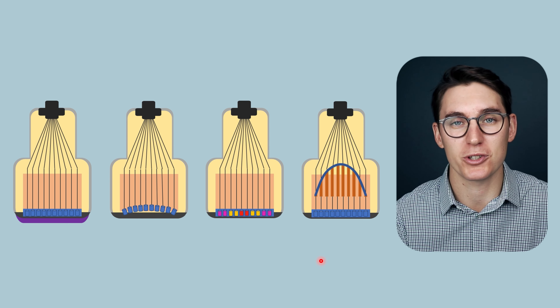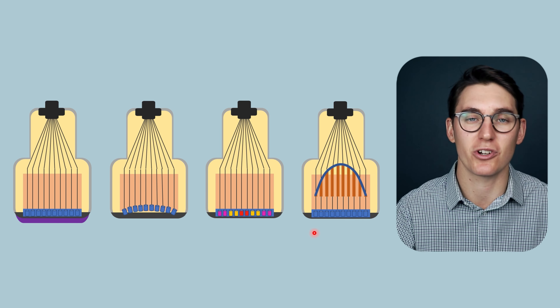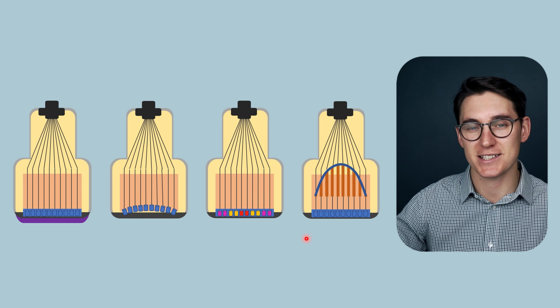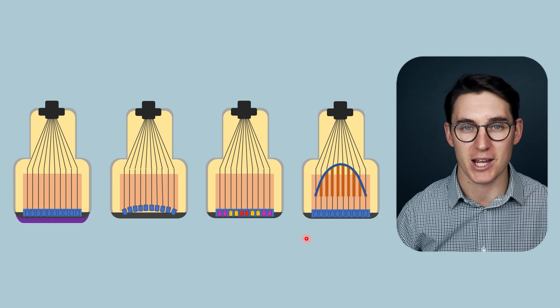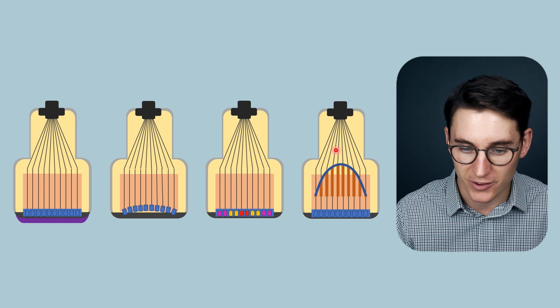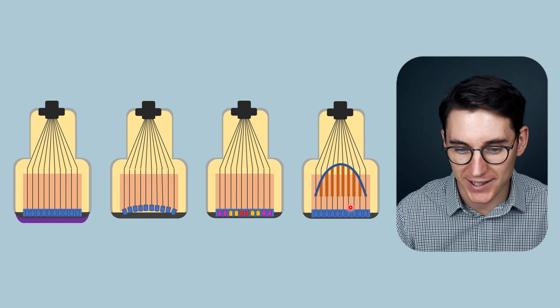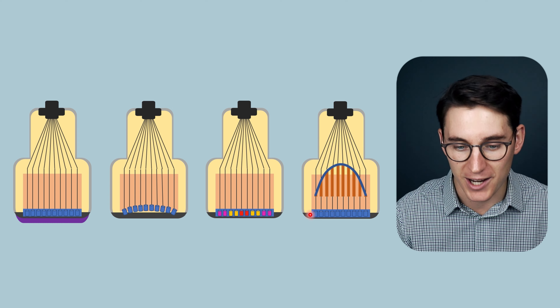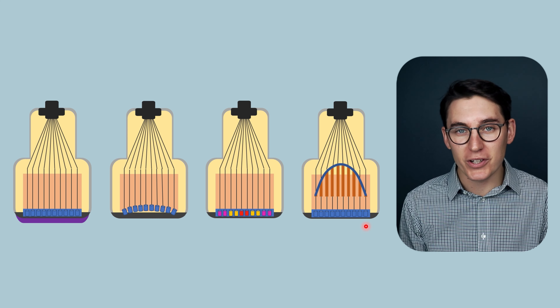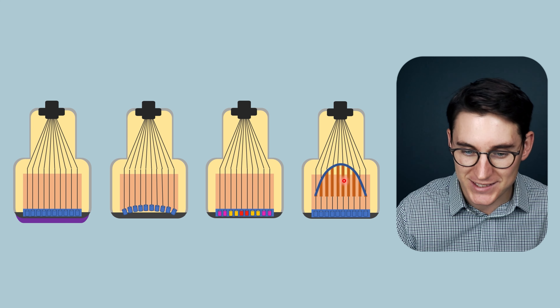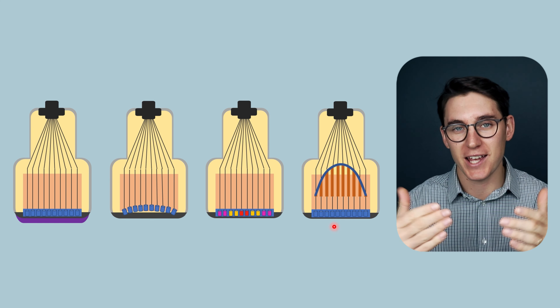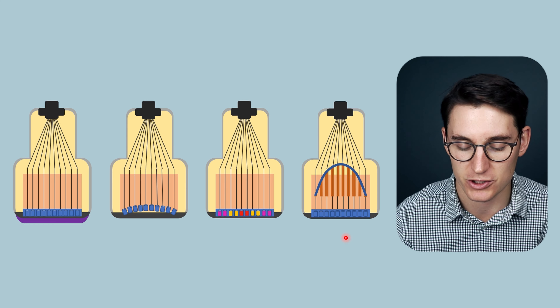The last and perhaps most important mechanism is electronic focusing. When taking an ultrasound, you can adjust the focal depth on the right-hand side of your image — that adjustment is largely done by electronic focusing. Electronic focusing works by delaying the central transducer element firing and firing the peripheral elements first. This delay increases the angle of focusing and brings the focal depth closer to the transducer.